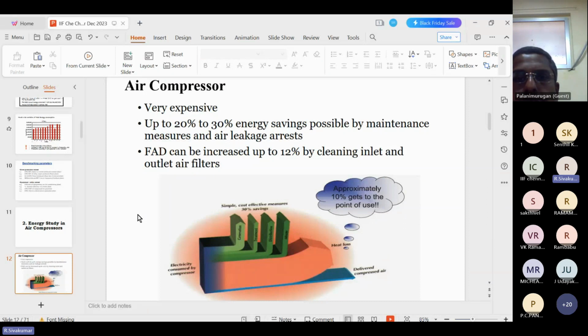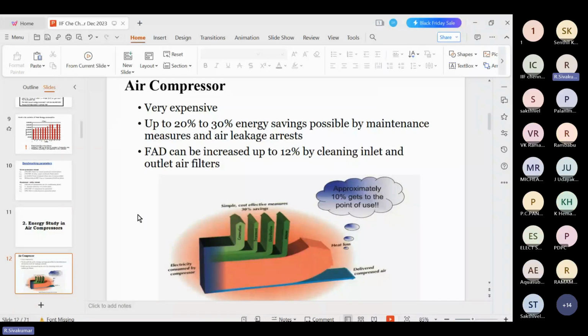The remaining 85 to 90% of the energy is wasted in generation, transmission, treatment and other hot areas. Whatever input energy is given to the compressor, only 10 to 15% is converted into useful air. For example, take a 100 HP, that is 75 kilowatt, air compressor. Based on the service factor, the compressor will draw around 105 to 110 kilowatt per hour. Out of this 110 kilowatt hour, only 10% of the input energy is converted into air, and all the rest is wasted as losses.